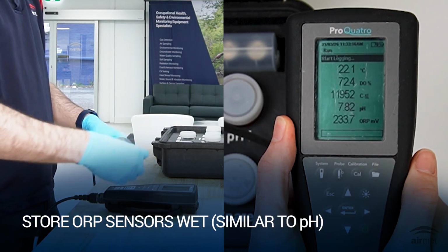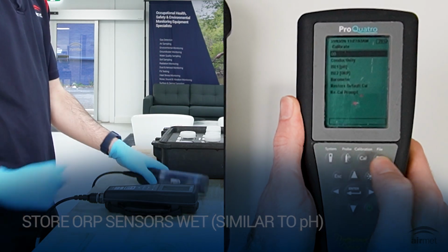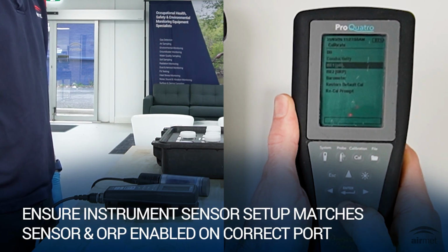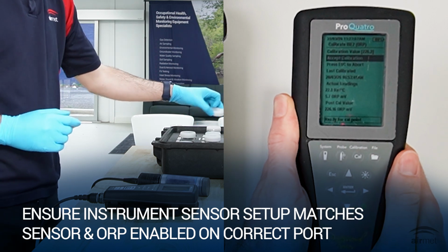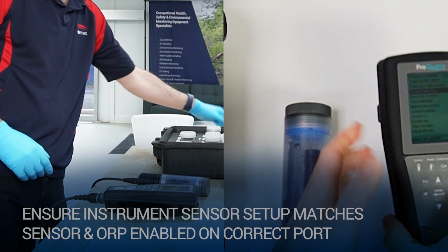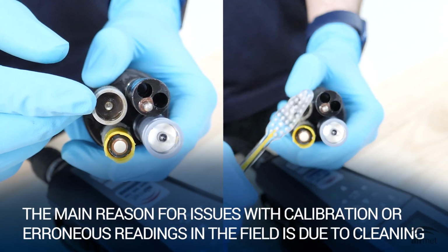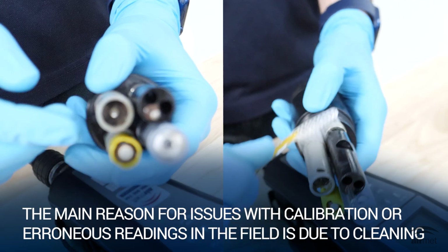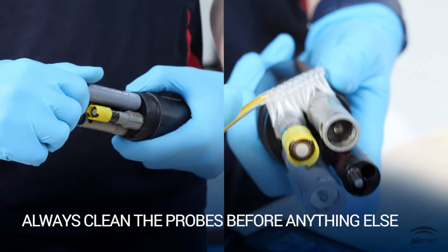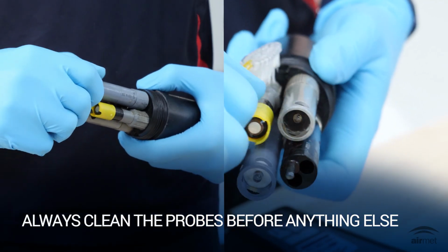Store the ORP sensors wet, similar to pH. Ensure the instrument sensor setup matches the installed sensor, and ORP is enabled on the correct port. The main reason for issues with calibration or erroneous readings in the field is cleaning. Clean the probes before doing anything. For cleaning tips, please see our video on best practices for calibration.